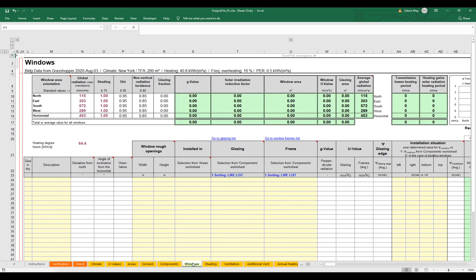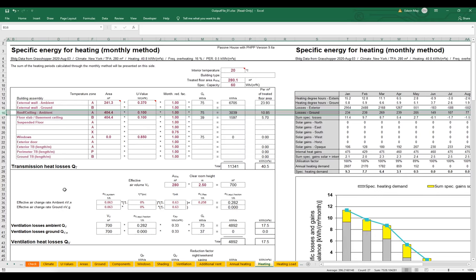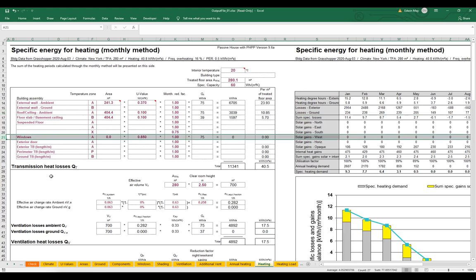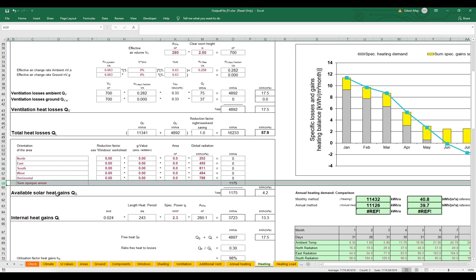We want to start adding some windows. If we scroll across to the heating worksheet — remember, this is just a review and visualization worksheet, we don't actually input information here — you can notice on line 21 that the window area is zero. We don't have any windows active, so they're not part of our overall annual heat losses. If we scroll down to our solar gains panel, we get all zeros except for the opaque areas, which see a small amount of solar gain as they heat up due to solar radiation. So we're going to see a lot more solar gain when we start adding windows.